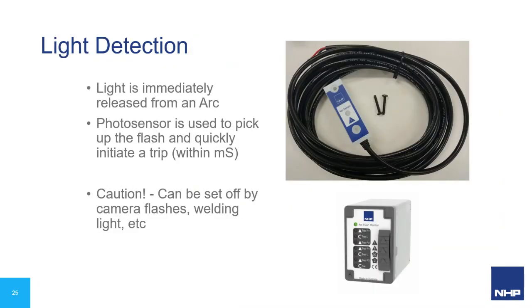So the most common mitigation strategy that's been implemented for a few decades now is light detection. Basically it's a photo sensor that picks up the blinding flash of light when an arc occurs, and it quickly initiates a trip. That can be within a few milliseconds. There is a bit of caution there: if you're taking photos, doing some welding or floodlighting nearby and that light gets into the switchboard, you can get a nuisance trip. But obviously, you should be taking a bit more care than that when you're looking at this sort of gear.